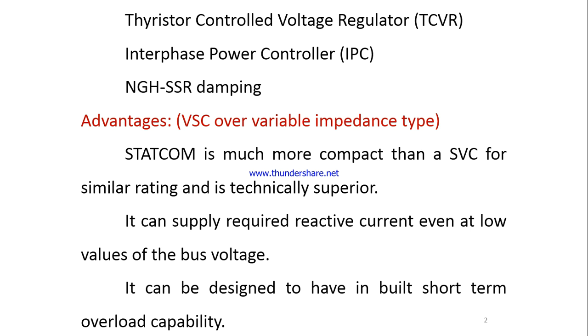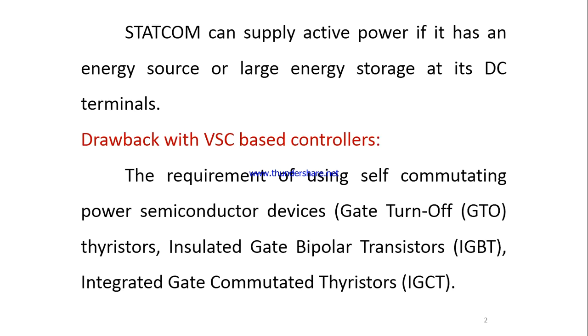The main advantage of VSC over the variable impedance type is that STATCOM is much more compact. It can supply the required reactive current even at low values of voltage. It can be designed with a short-term overload capability, and STATCOM can supply active power even if it has an energy source or large energy storage at its DC terminals. But the main drawback is that self-commutating power semiconductor devices, the GTO, thyristors, IGBT, and IGCT, are very necessary, and they themselves have their own limitations. So this is the main drawback for VSC based controllers, because they are totally dependent upon the power electronic devices.